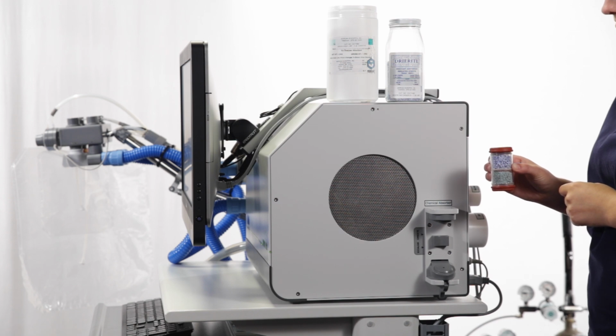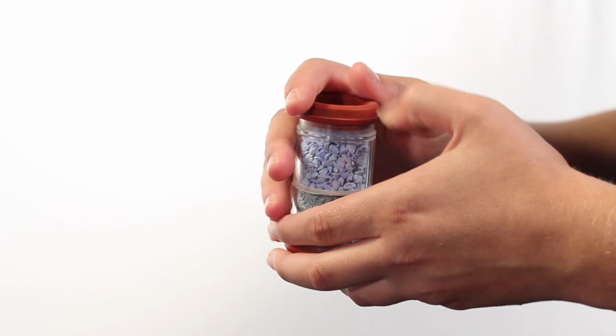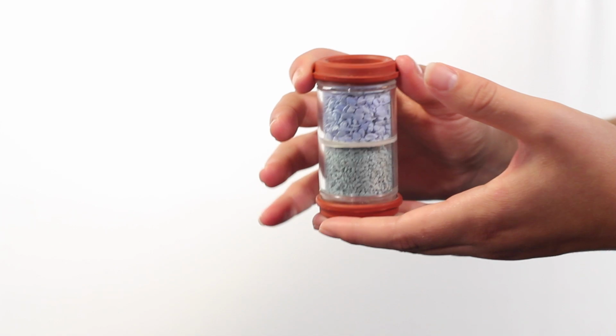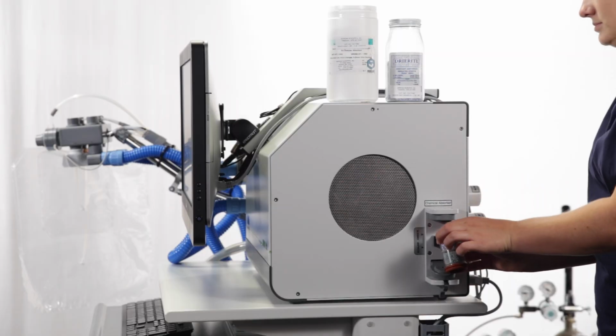Care should be used when handling the chemicals. If you come into contact with soda lime, be careful to wash your hands. When filling the absorber, leave a 1/4-inch gap at the top of the tube so that the rubber gasket can seal properly.